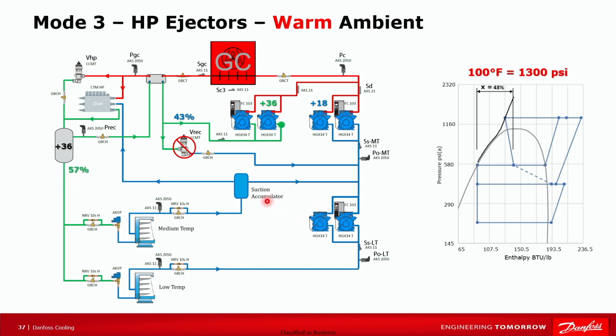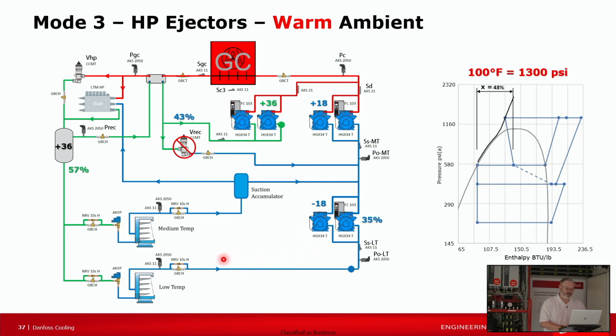I spoke too soon. We're going to look at the 57% liquid right quick to help explain the ejector. So of that 57% liquid going to the evaporators, the low temp makes up about 35% of that. The medium temp is going to make up about 22% of that. So at this point, the refrigerant coming from the medium temp evaporators has a decision to make. Do I go to the plus 18 at 400 pounds, or would I go somewhere else?